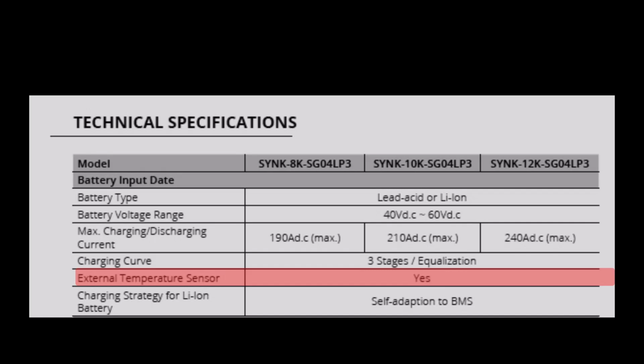The third stage is called the equalization stage, and for a short period there's a much higher voltage, to make sure that all the battery cells are equally charged until it gets up to 100%. This keeps the battery healthy and efficient and is common to most modern batteries.